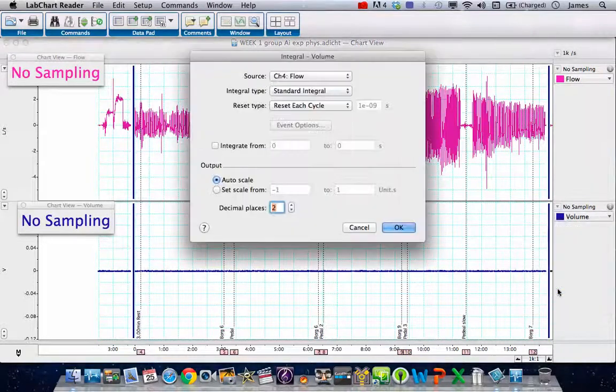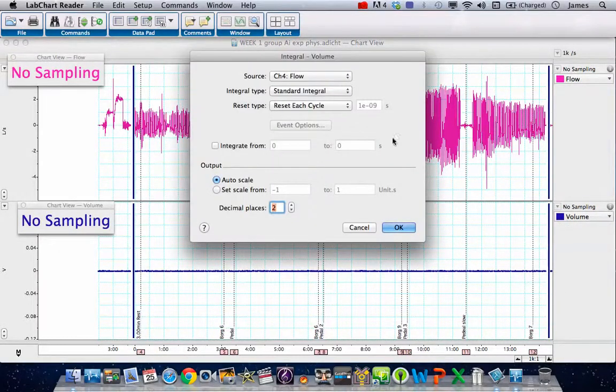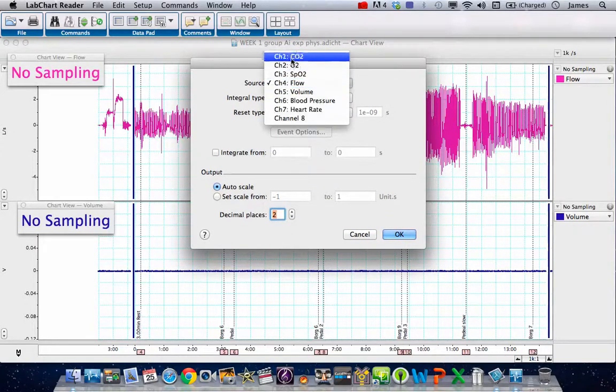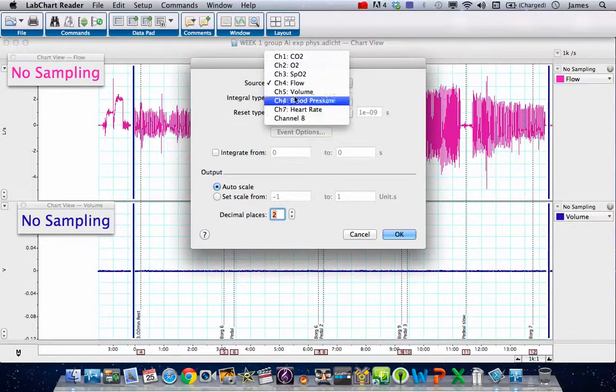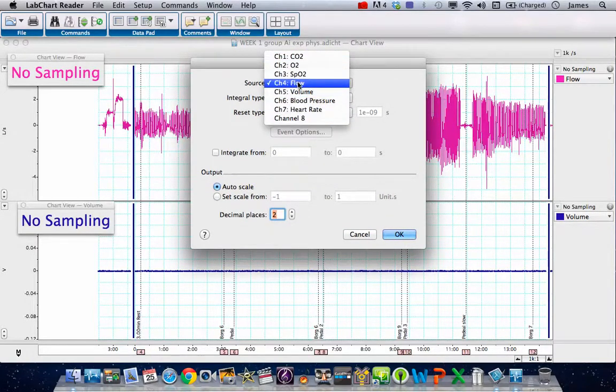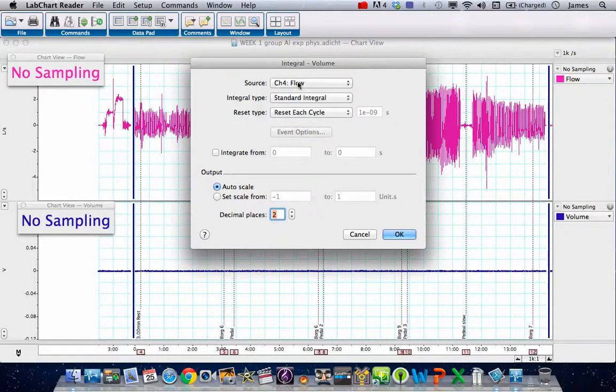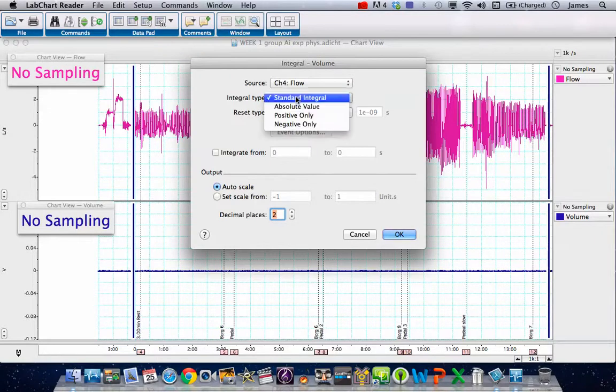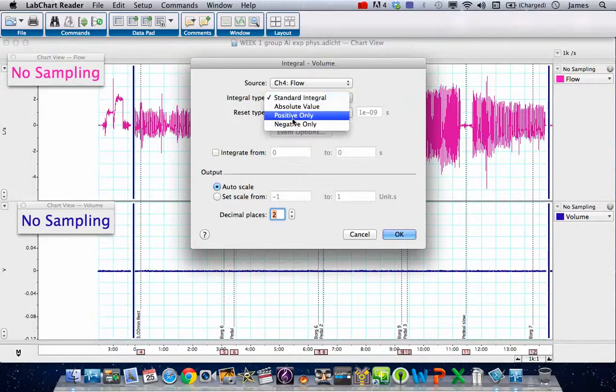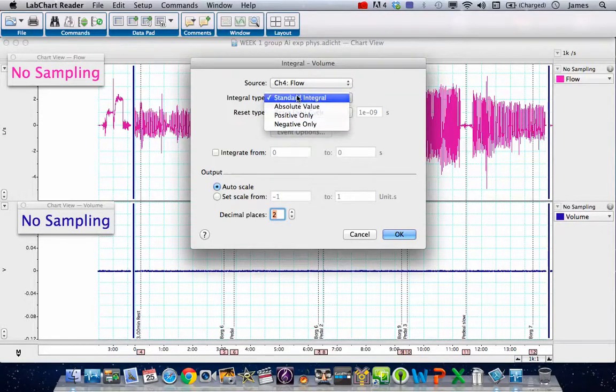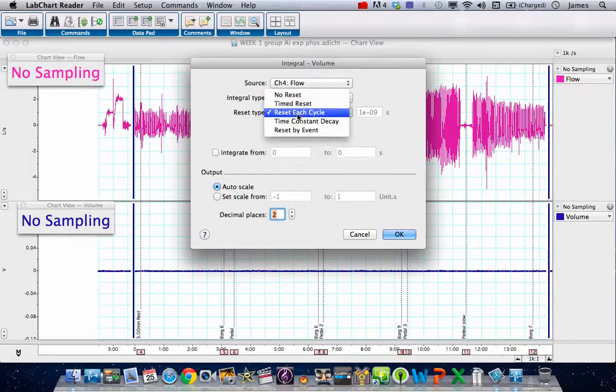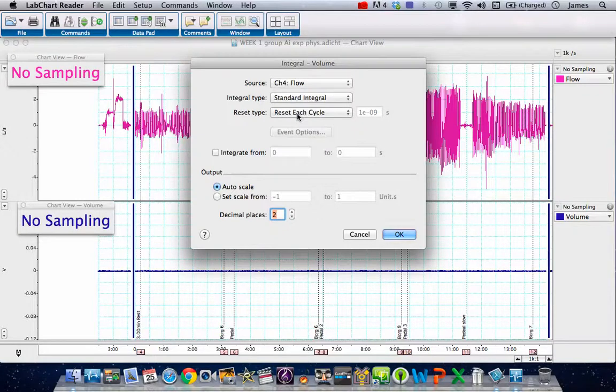We click on the integral and it brings up the standard integral option box. The source of our data can be any one of our channels, but we want it to be channel four, which is our flow which we've just calibrated. We want to choose an integral type of a standard integral. We don't want to worry about positive or negative, so we're going to choose standard integral. There are some problems with drift potentially, but we're going to choose that we're going to reset each cycle.